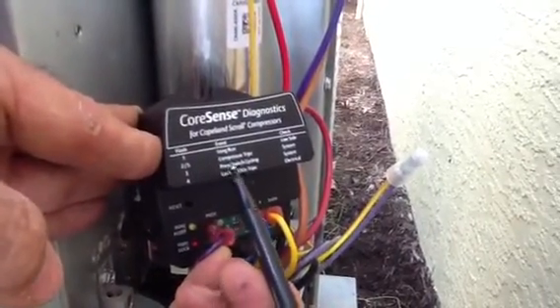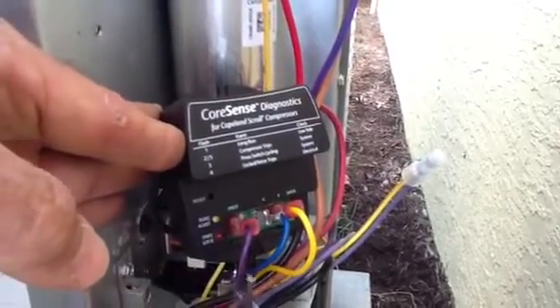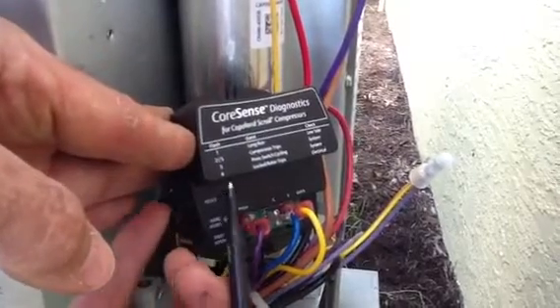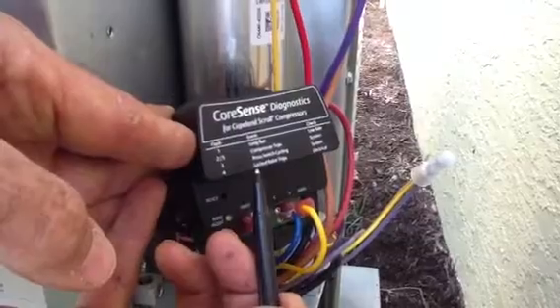If you have three flashes, that's pressure switch cycling — it's going to be cycling on and off repeatedly, indicating there's an issue with other things. Then you've got four flashes, which is locked rotor trips.